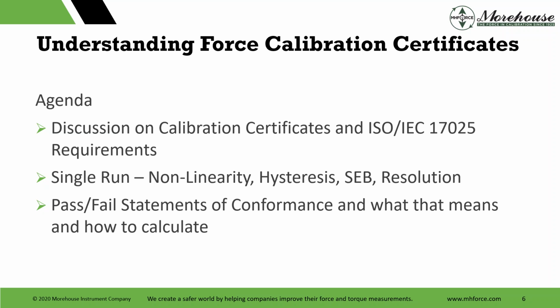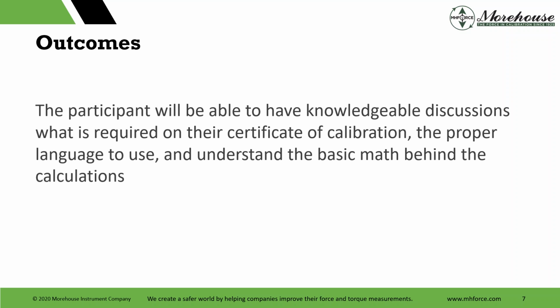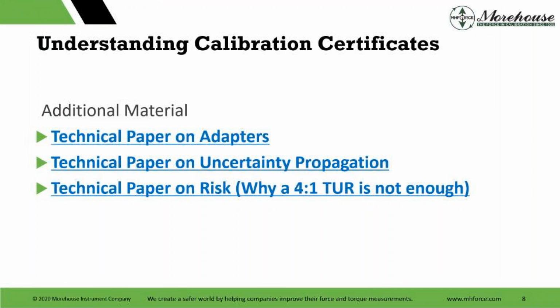We're going to talk about single-run calibration certificates, specifically non-linearity, hysteresis, SEB, and resolution. We're going to talk about pass-fail statements of conformance, what that means, and how to make some of those calculations. The participant will be able to have knowledgeable discussions of what is required on their certificate of calibration, the proper language to use, and understand the basic math behind some of the calculations.